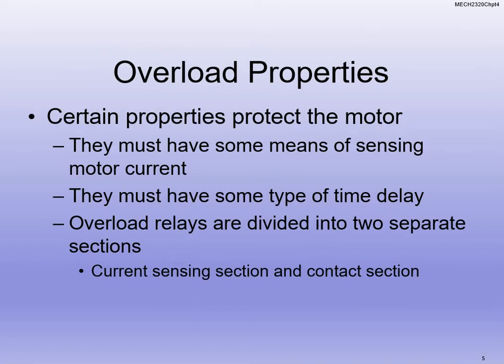With overloads, they have some sort of way to detect the motor current. So every single overload we're talking about, even fuses and circuit breakers, we're detecting the amount of current. They don't have a current reader on them, but based on our properties of current, current gives off heat and it gives off a magnetic field. So we're going to use those two things to help protect our equipment. We have a current sensing section, which is the field or the heat given off, and then we have a contact section. What that's for is so we can understand in the PLC what happens. So we have communication with the PLC as well. We physically protect the device, and then we let the PLC know, hey, this is what tripped, and here's why.